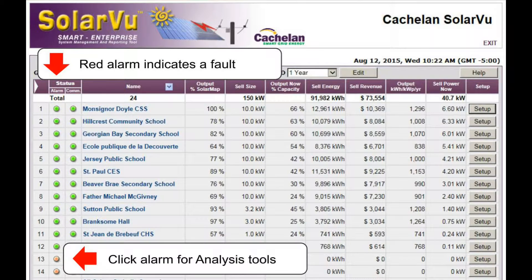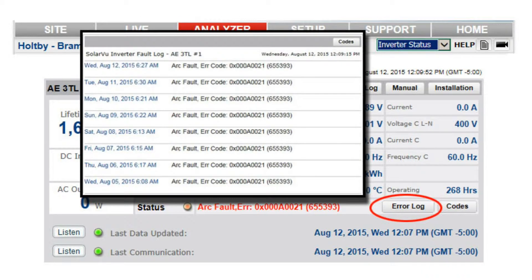When a fault is detected at a site, an email will be sent and its alarm status light goes red. Click on the alarm indicator to go to the analyzer tools for troubleshooting details like the inverter status, which will display the alarm cause. Check the error log for a list of recent faults. Once the condition is fixed, the indicator will go back to green.